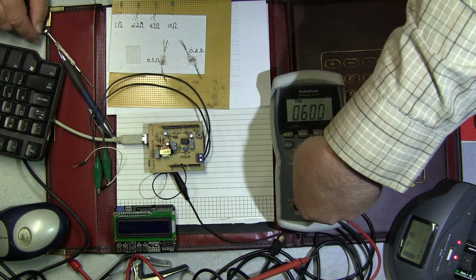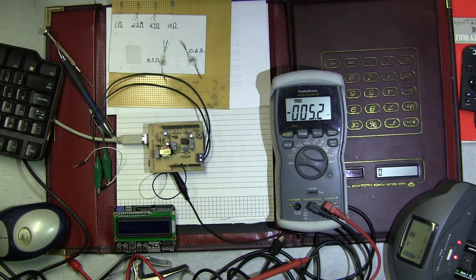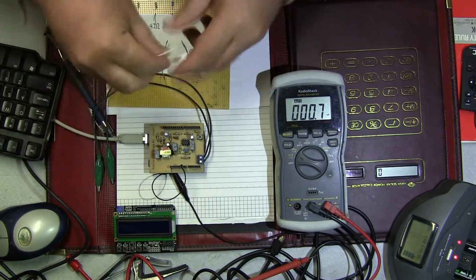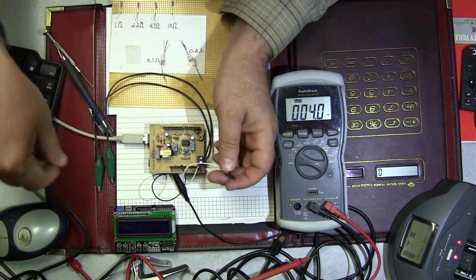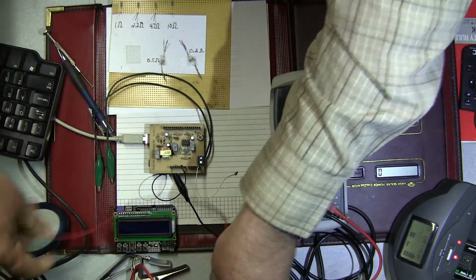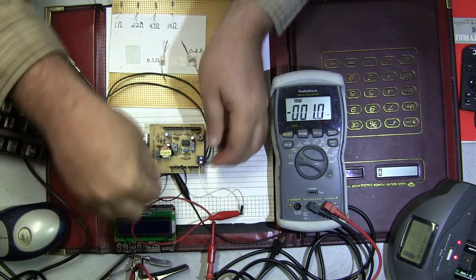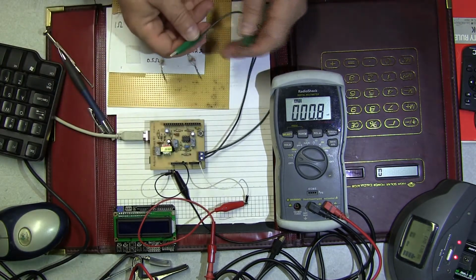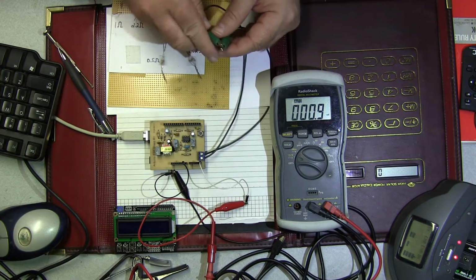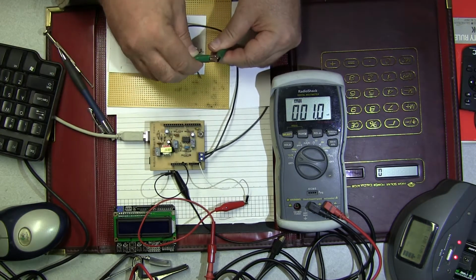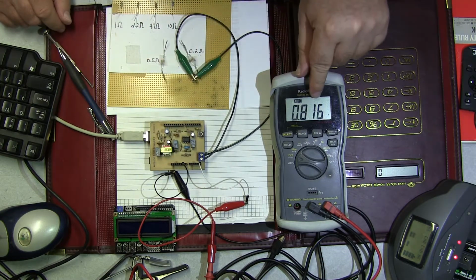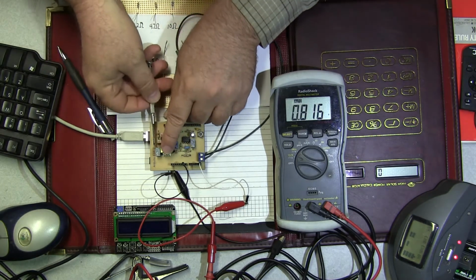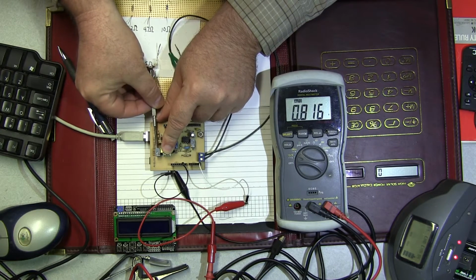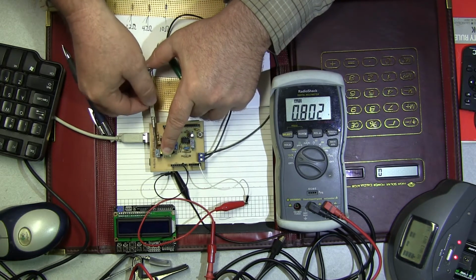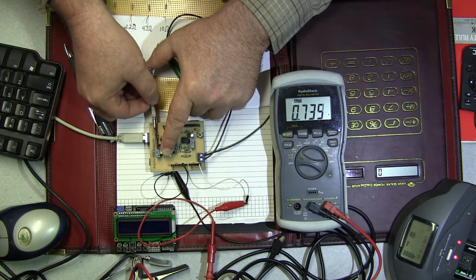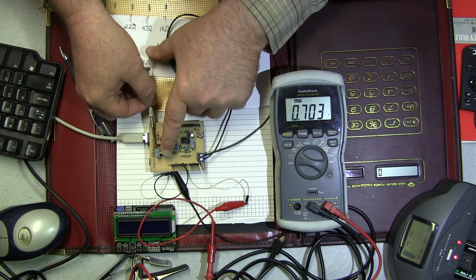Okay, so we can go ahead and switch back to our millivolt range, DC millivolt if you have it. Okay, go ahead and put our probe back in pin 5. Okay, and the first value we want to set is the output of the op amp. So what we're going to do is we're going to short our leads out, and we're reading 815 millivolts. We want to turn this load pot until we get that dialed down to around 700 millivolts. That's the wrong way. Okay, so there's 702. That's plenty close enough for right now.